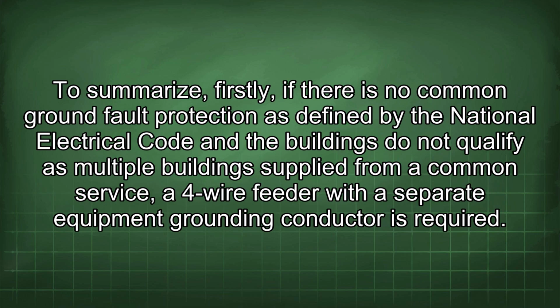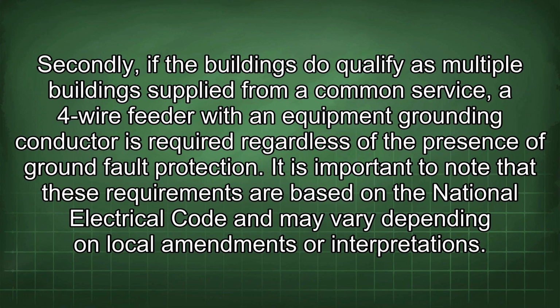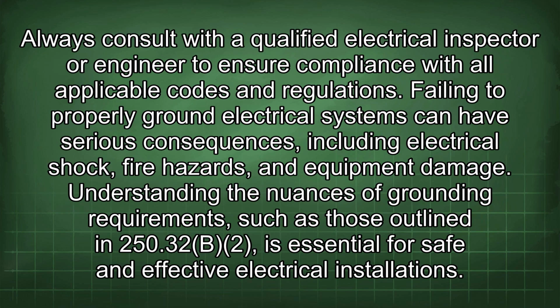To summarize, firstly, if there is no common ground fault protection as defined by the National Electrical Code and the buildings do not qualify as multiple buildings supplied from a common service, a 4-wire feeder with a separate equipment grounding conductor is required. Secondly, if the buildings do qualify as multiple buildings supplied from a common service, a 4-wire feeder with an equipment grounding conductor is required regardless of the presence of ground fault protection. It is important to note that these requirements are based on the National Electrical Code and may vary depending on local amendments or interpretations. Always consult with a qualified electrical inspector or engineer to ensure compliance with all applicable codes and regulations. Failing to properly ground electrical systems can have serious consequences, including electrical shock, fire hazards, and equipment damage.